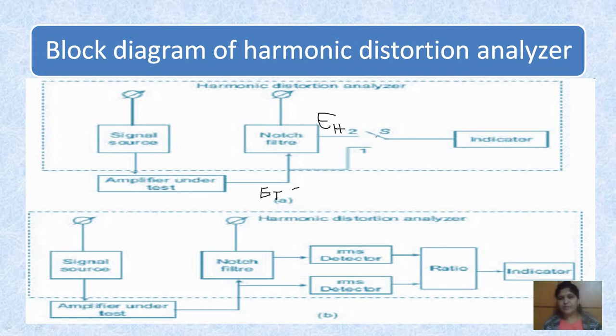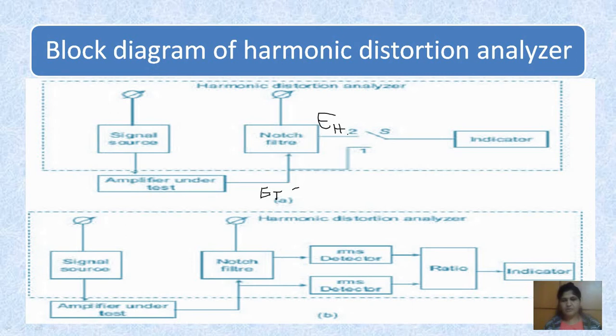There is a manual switch. If you want to find the total distortion — that is fundamental plus harmonics — connect to switch position one. If you want only the harmonics, connect to switch position two, and the indicator will display the result. Switch position one gives the total amplitude ET, and switch position two gives the amplitude of the harmonics EH.